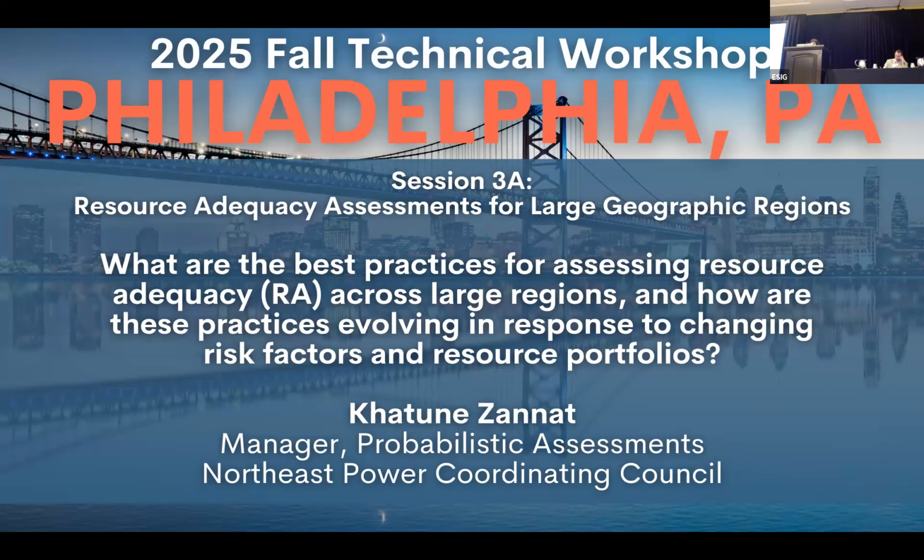NPCC performs a long-range adequacy overview. That's the second report I was highlighting, looking over 5 years ahead for expected demand. That's your 50-50 conditions, as well as we do a probabilistic assessment looking at extreme demand forecast. And we evaluate for each one of the 5 areas whether they are meeting the industry standard loss of load expectation of 1 day in 10 years criteria.